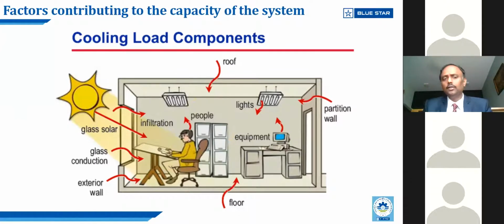Second, the number of people inside plays a very important role. More people means more tonnage required. The lighting load also plays an important role. Then whether the building is on the topmost floor, exposed to sunlight, whether it's on the ground floor, or whether there is a floor below - all this decides the total capacity of the system.